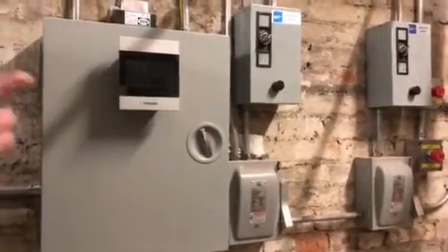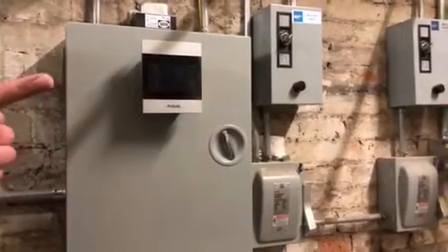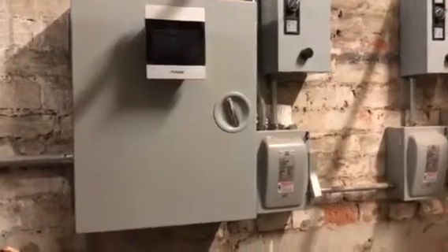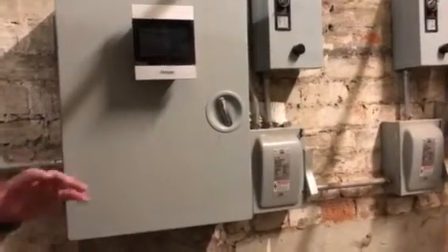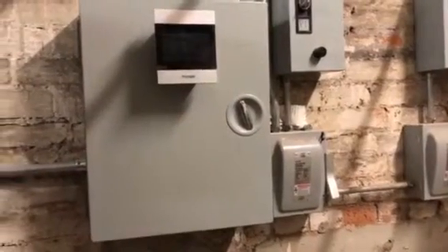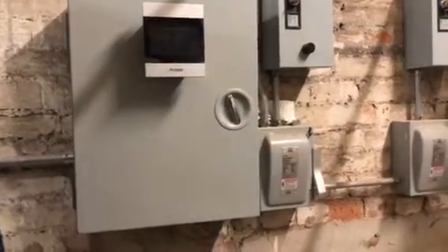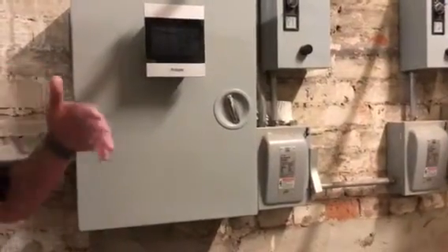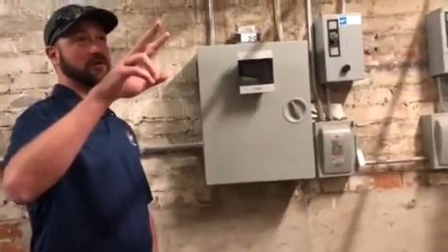One thing we added was combustion air dampers over on the wall. Before it was just wide open. This room was always freezing cold. So now we're actually controlling those dampers. 50% of one damper per stage. There are 4 stages, so those dampers can be in 4 different positions, either fully closed, half open, or fully open. We are controlling both of these pumps.